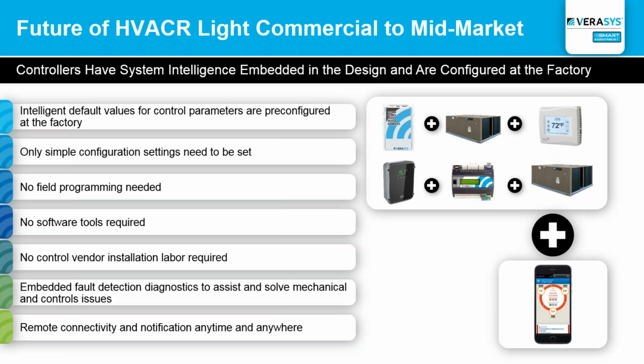Think about the value proposition there: when servicing a rooftop, if you know in advance whether you have a refrigeration leak, too much refrigerant, or a heat transfer issue, and you can remotely connect to the system to understand your superheat or subcooling, that's the kind of information that makes the system very powerful.